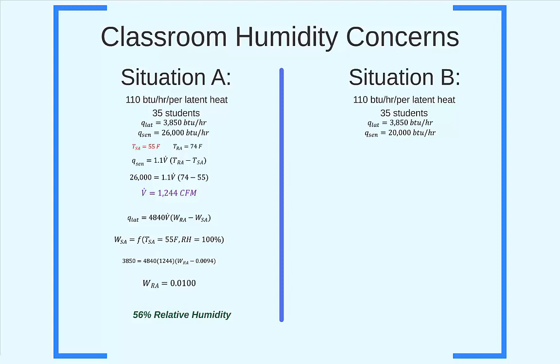If the reset schedule was quite aggressive and forced a 65 degree supply air temperature, what effect would that have on our room's humidity level? Well, let's see. Going through the same set of equations as before, we find the required flow rate has now increased to 2,020 CFM. We will come back to that value here in a minute. First, let's try to figure out the room's humidity level.